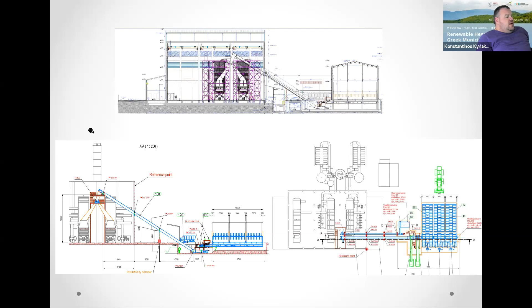Finally, here we can see all the possible fuels we use for the boilers. These are actual values, and the prices are real prices we pay to purchase these fuels. The lignite we use has a calorific value of 2.5 megawatt hours per ton, and we buy each ton of lignite at about 34 euros, so we buy energy from lignite at about 13.5 euros per megawatt hour.